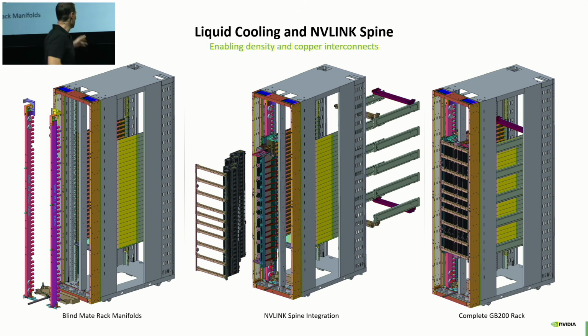You also see on the manifolds quick disconnects supporting the full complement of nodes we can put in the rack. Each disconnect requires around 40 pounds of mating force. It doesn't sound like a lot for a stainless steel tube, but when you stack 48 devices and add it all up, those tubes move—enough to matter. So we build in support bracing behind the manifolds to support it across that span; otherwise there'd be multiple millimeters of deflection.